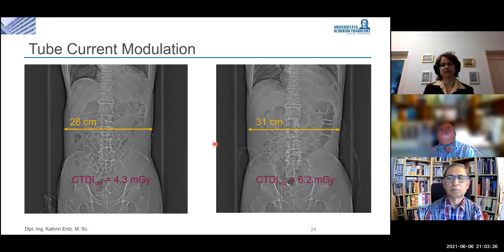And for the CT scanner, it is now a bigger patient, and that leads to a higher dose value of 6.2 milligrays. So you have 50% dose increase just because you're not properly positioning the patient, and just those 3 centimeters result in 50% more dose. So the tube current modulation is a very good tool to adjust the dose, but it also has some sources of error where you have to check regularly and perhaps train your radiographers if it's not working in a good fashion.